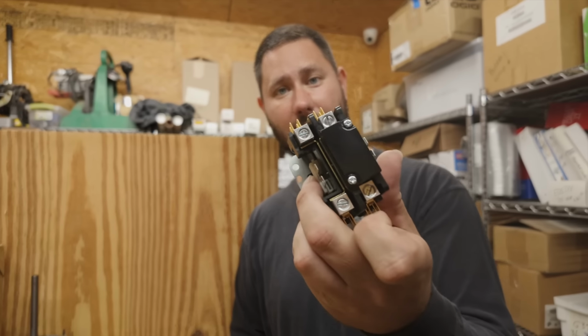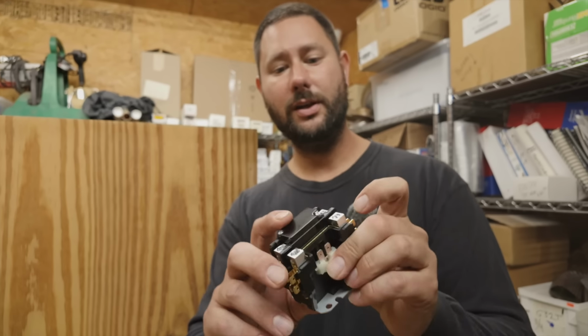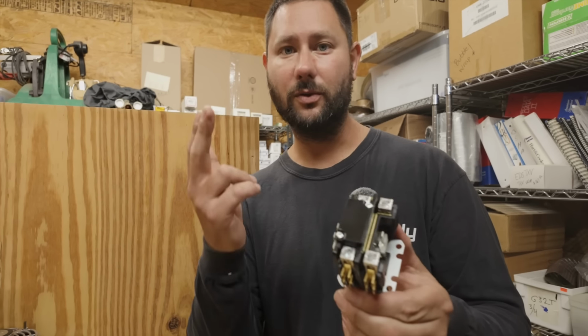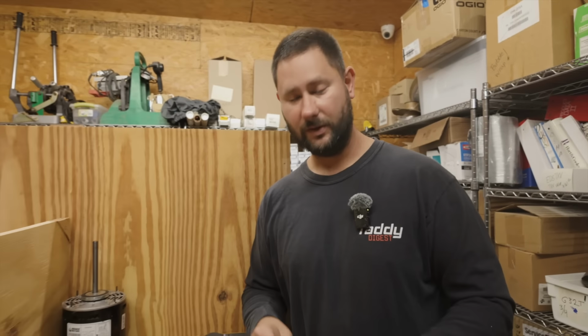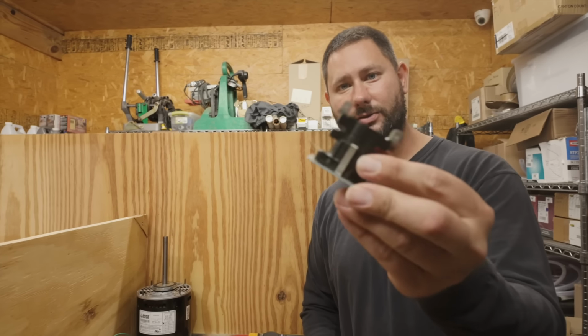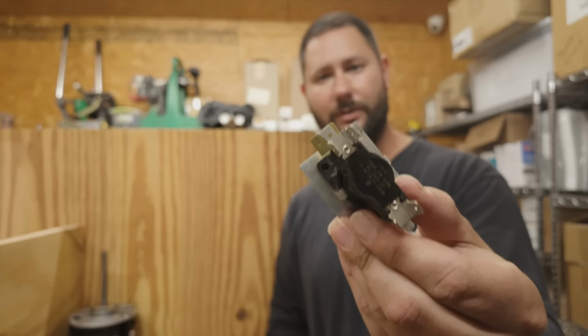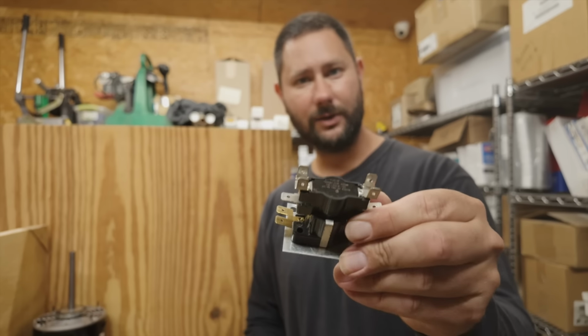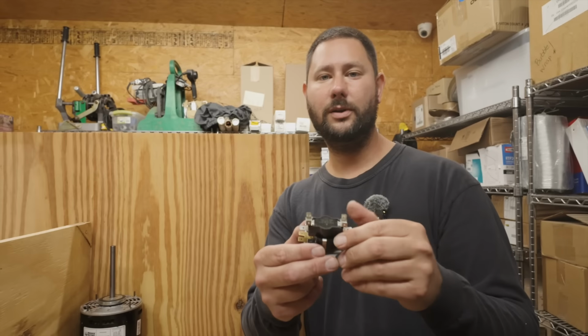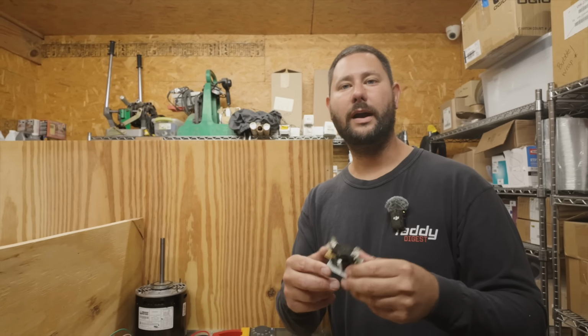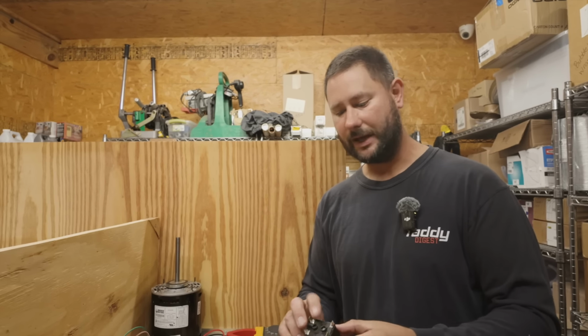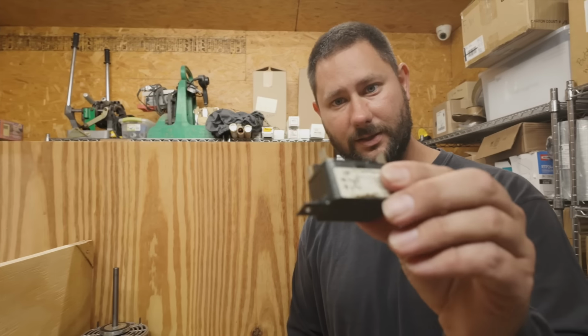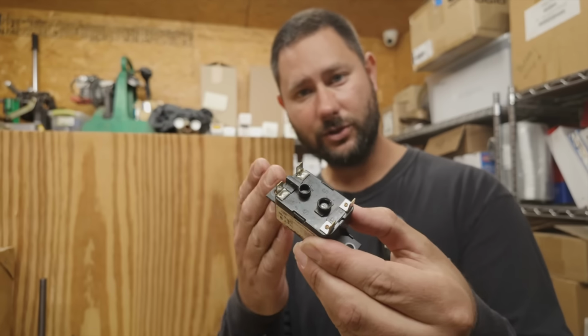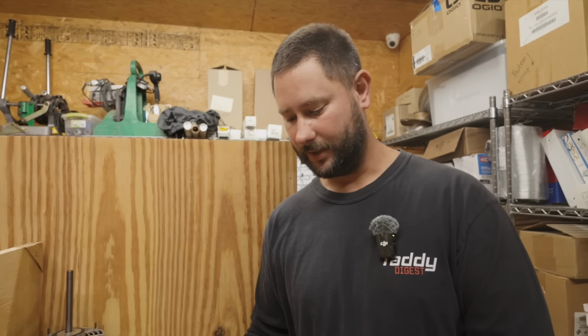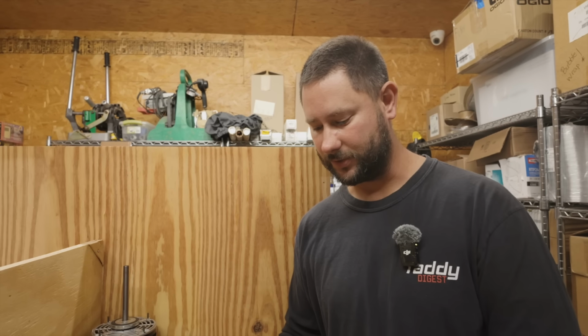Second is a contactor. This is typically used to power a compressor or a fan motor. Then we've got a sequencer. This usually has a delay. You see these in electric furnaces, maybe part of a heater kit, and this is used to power a fan motor or a heating element. Then we've got a fan relay. This is a little simple relay, usually to control a fan motor. You see these in different residential systems.